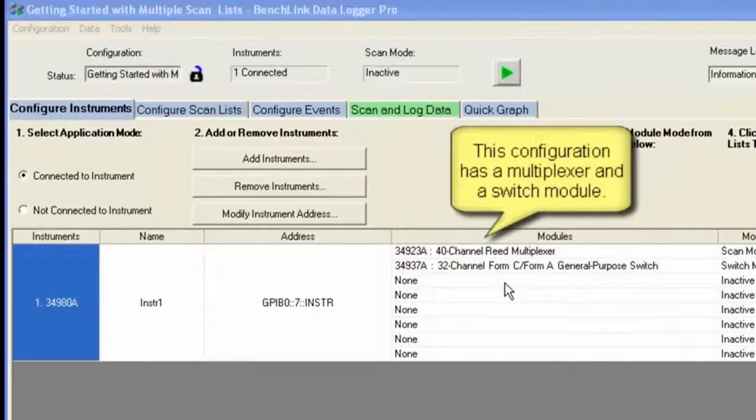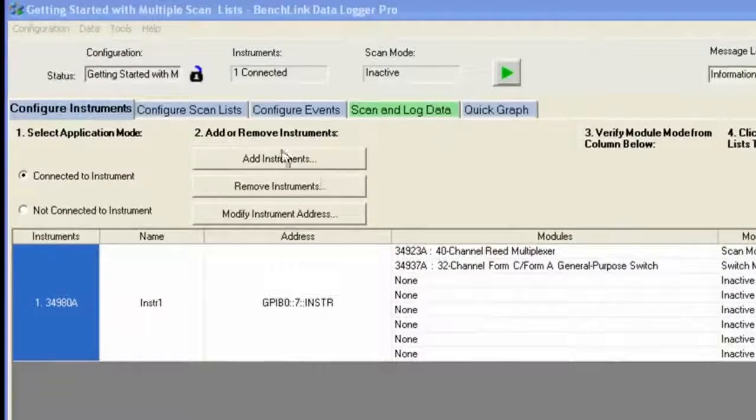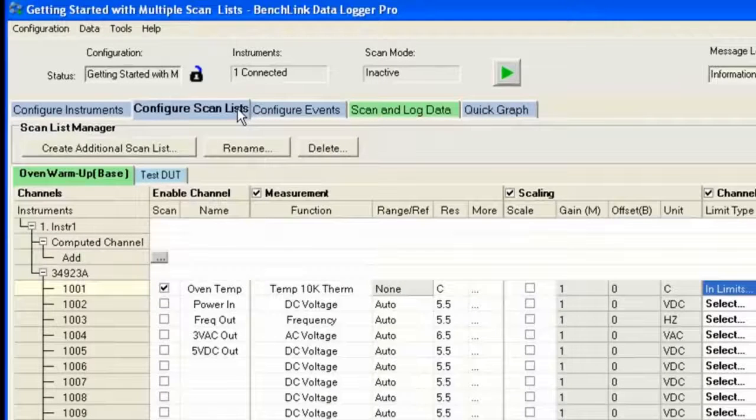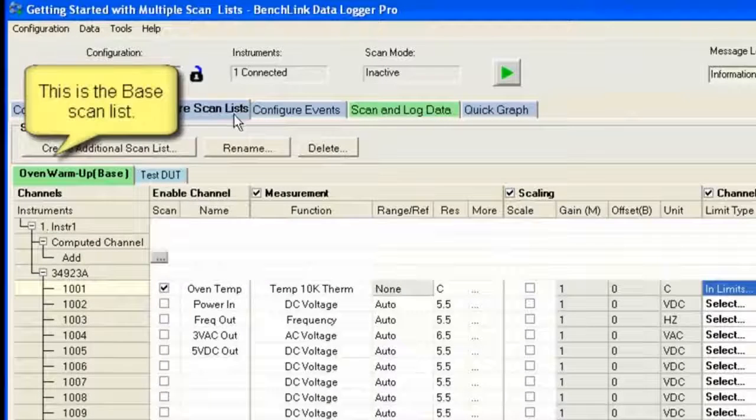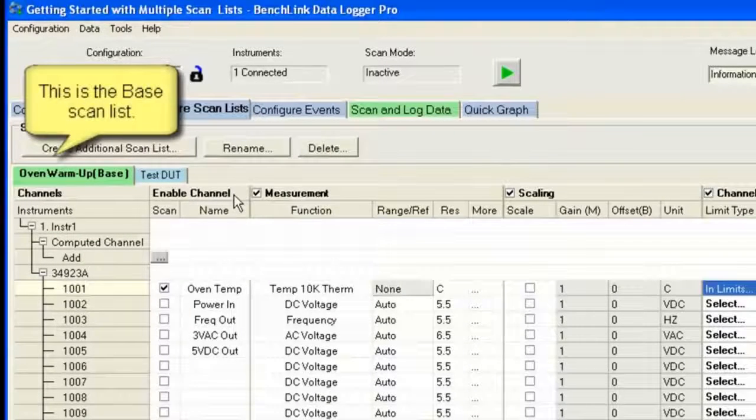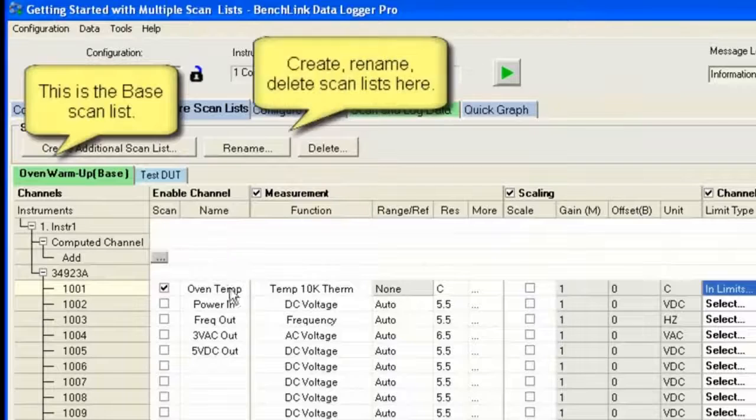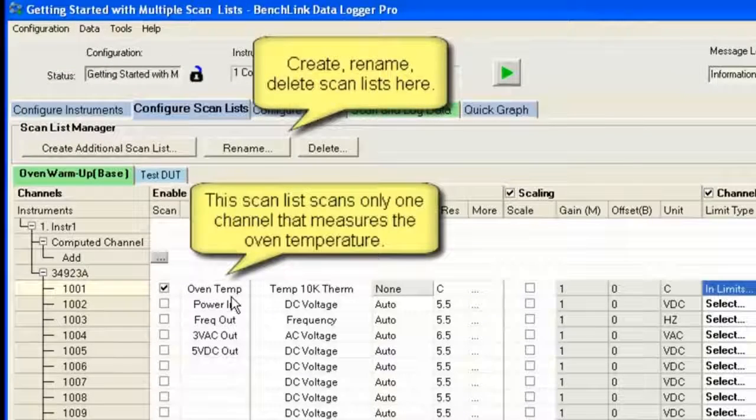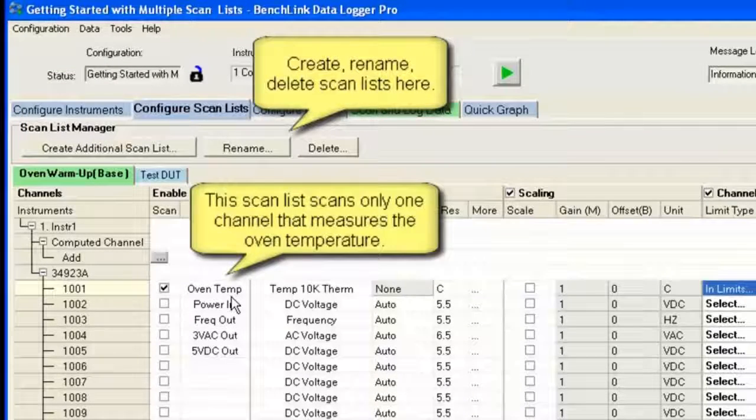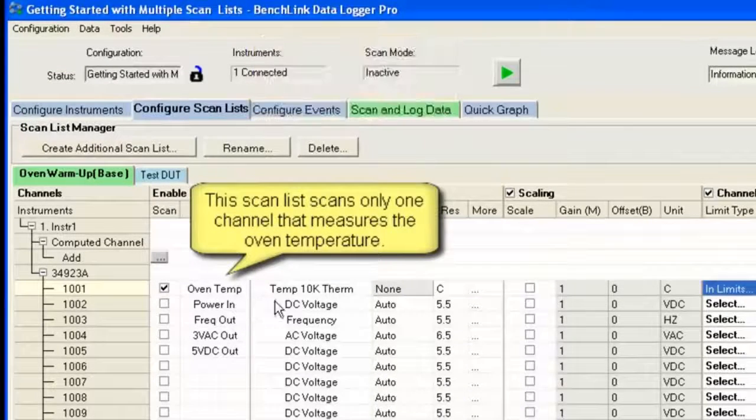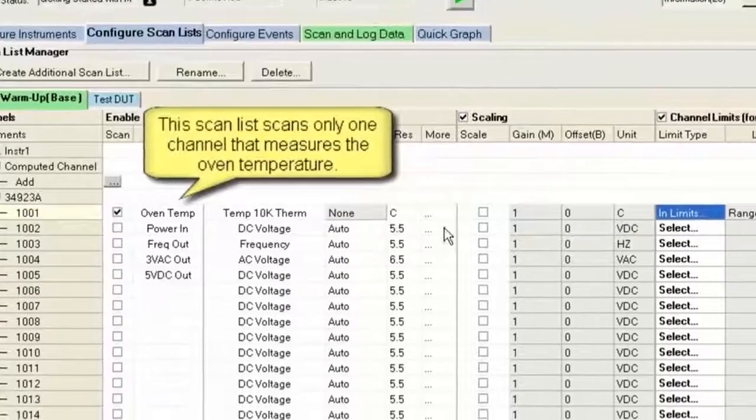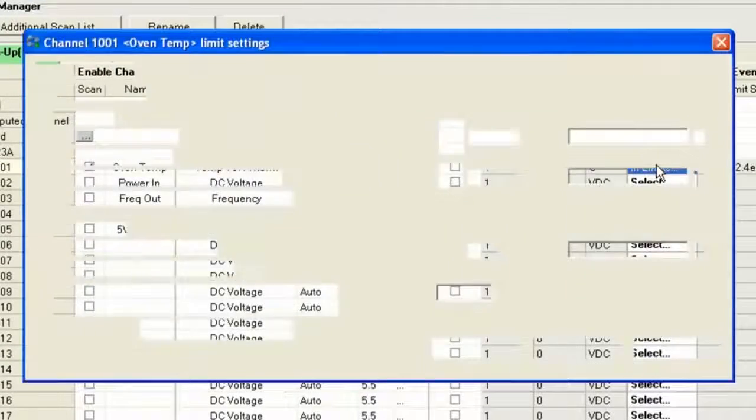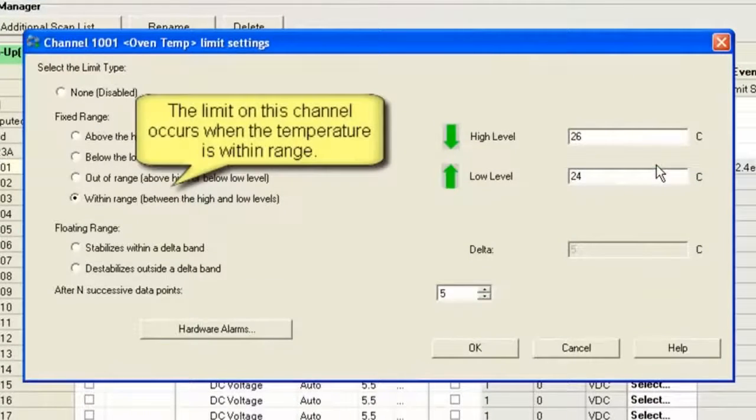We've already connected to our 34980A. It's an eight-slot mainframe. We have two slots filled with two different modules. I'm going to look at the first scan that we're going to run. The first scan is going to monitor oven temperature. We're going to monitor it with a 10K-ohm thermistor. It's going to scan that one channel.